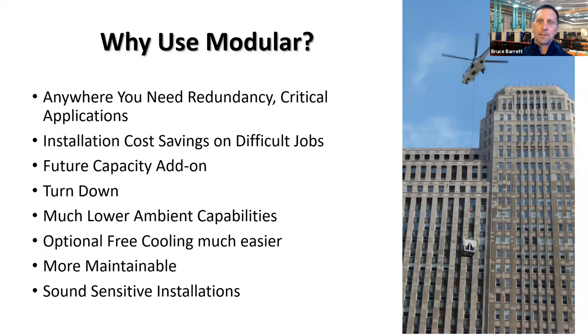And lastly, sound sensitive installations. Air-cooled chillers are outside. There are often sound boundary requirements in different municipalities. There might be flat out sound requirements for a manufacturing facility. People are becoming more aware of damage to the ear from prolonged sound coming from air-cooled chillers. We've got some ways to compensate for that.